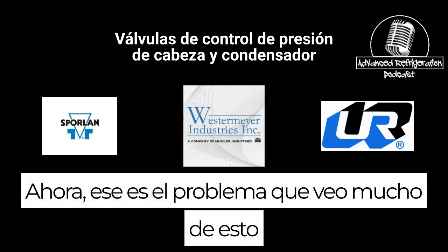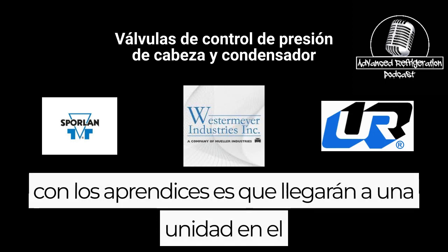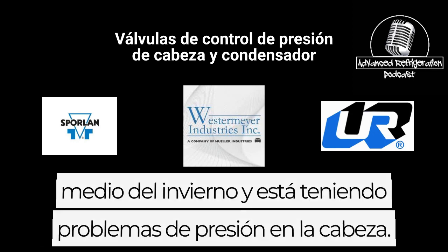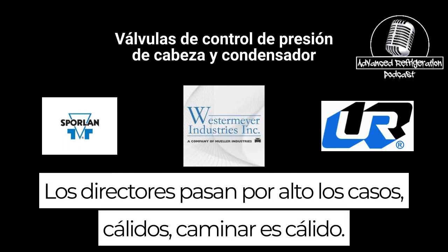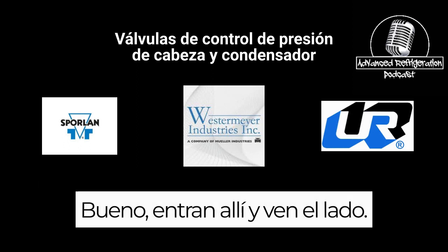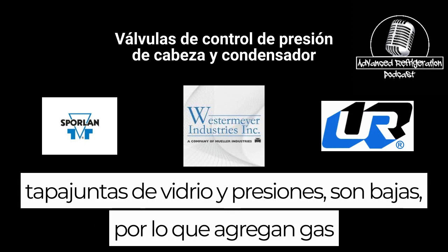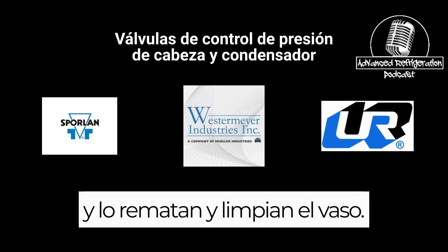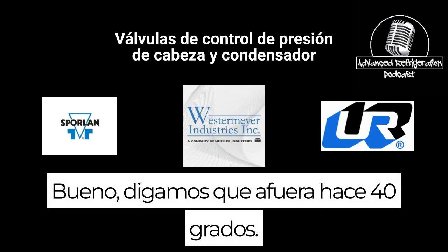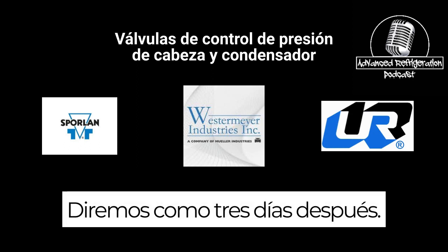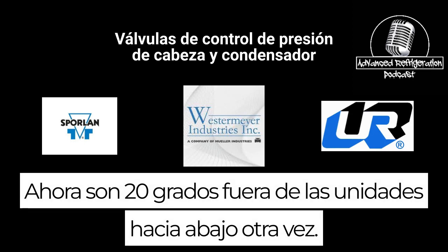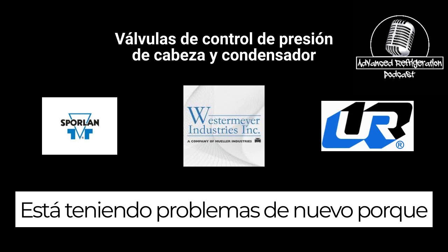Now, that's the problem I see a lot with apprentices. They'll get to a unit in the middle of wintertime and it's having head pressure problems, the headmaster's bypass face is warm, the walk-in's warm. Well, they go in there and they see the sight glass flashing and they see low pressures. So they add gas and top it off and clear the glass. Well, say it's 40 degrees outside. Say 3 days later, now it's 20 degrees outside. The unit's down again. It's having issues again because it didn't have enough liquid in it.